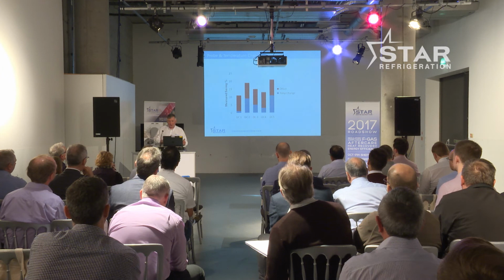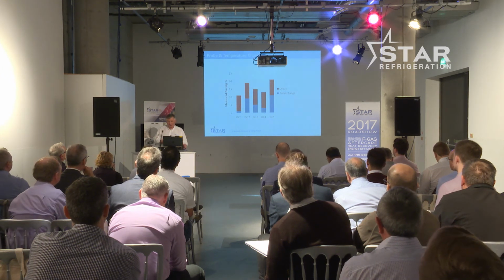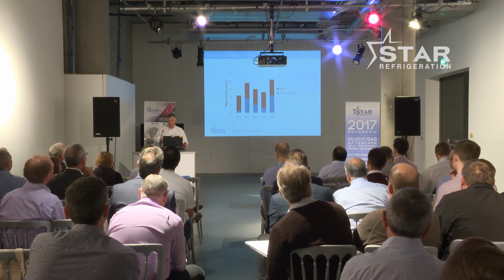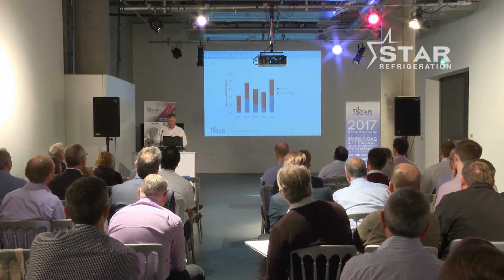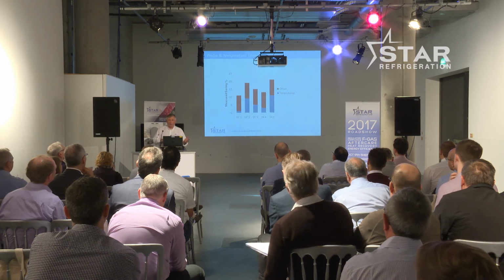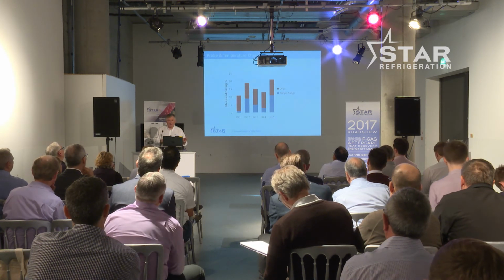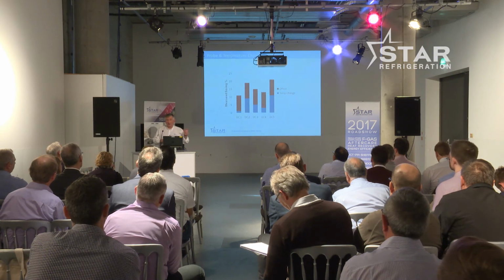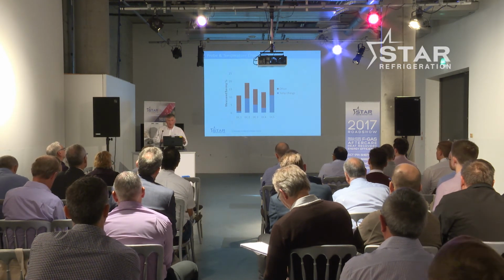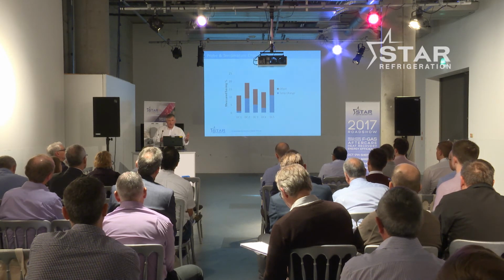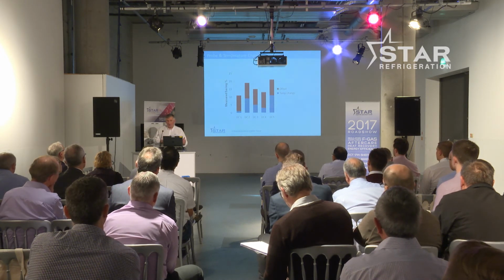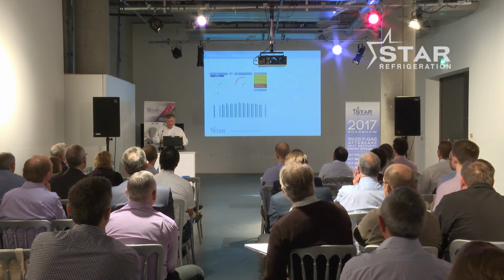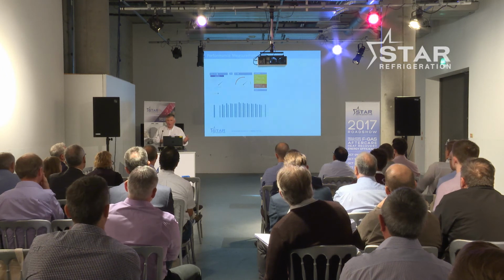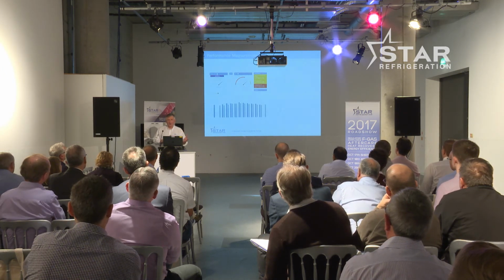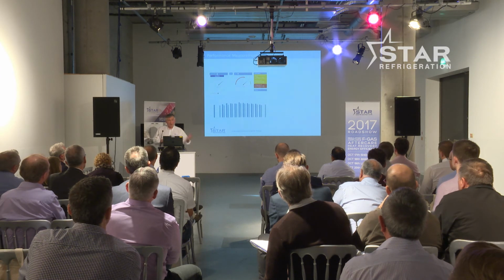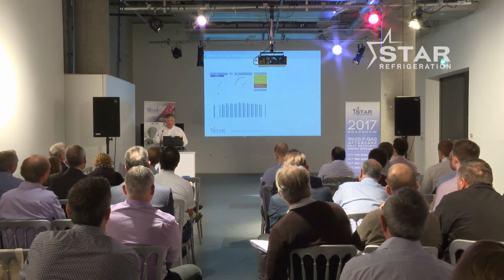And on average, the saving of the offset was 7% across the 5 DCs. So that is in line with the 3% figure per degree C. If you're running at -20 and you can run at -18, you could expect to save about 6% of your energy consumption. And that's why we say 10% is not an unrealistic number to achieve. So a key aspect of energy saving, and we're just moving to the conclusions now, is understanding the current situation, making changes, and then being able to make a comparison. How was it before and how is it after?